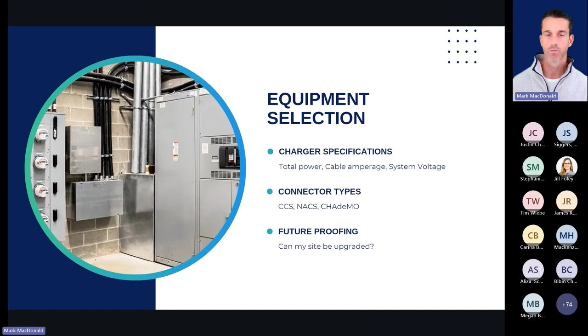Equipment selection - these are some standard breaker sizes, full side load calculations, and we can share this with anyone, including the presentation. Calculate kVA and then their closest transformer size. So if we start down at a 30 kilowatt DCFC, you're talking about 45 kVA for that supply transformer.